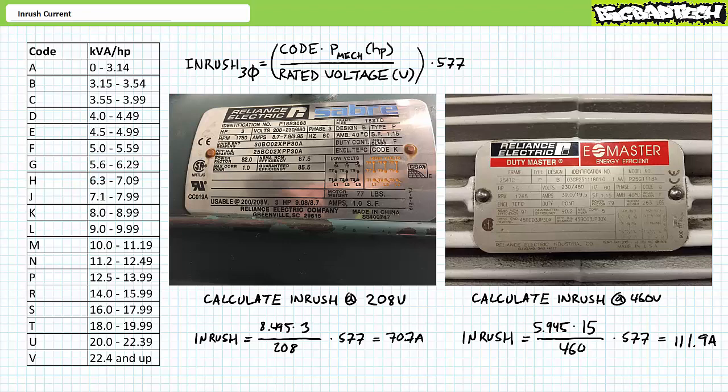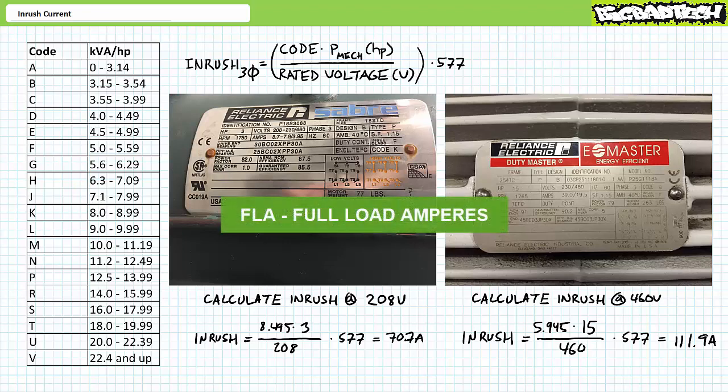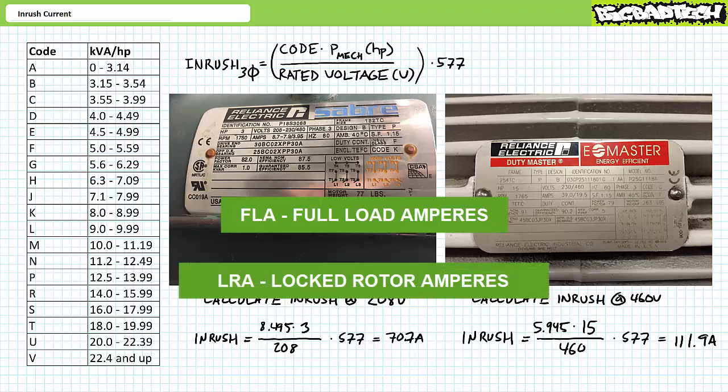It should be noted that some motor manufacturers take it upon themselves to perform inrush calculations in advance and explicitly state the expected inrush right on the motor nameplate. The entry FLA stands for full-load amperes — another way of stating rated current, meaning it is the current drawn per phase when the motor is producing its rated mechanical power output. If you ever see the entry LRA, this is the inrush current, where LRA stands for locked rotor amperes — the magnitude of the momentary surge of current drawn per phase when the rotor is locked and the motor is suddenly energized by full voltage. The LRA entry on the motor nameplate saves you the trouble of performing inrush calculations yourself.